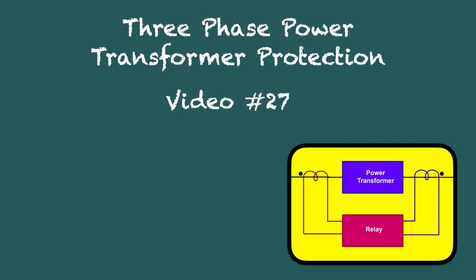However, I'm going to show you some relatively new transformer relays that are called IEDs, or Intelligent Electronic Devices, that are basically computers that work extremely fast and provide a multiple of functions for the protection of transformers. We're also going to look at the oil flow protection, the Buchholz relay, which is used in most of the oil immersion transformers that exist today.